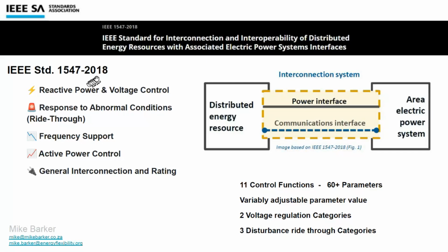So if you looked at the 2018 version of 1547, there's 11 control functions, and you can set 60 parameters. So you can really fine-tune this particular standard and the way your inverter sings and dances with the grid using the different control functions and the 60 or so parameters that give you a lot of leeway. And all these parameters are adjustable. There's a couple of voltage regulation categories, 2 of them. And then the important ride-through, there's 3 different categories there as well. So if you had to ask me what 1547 is about, I'd show you the slide and say, great, guys, here it is, this is what it does.